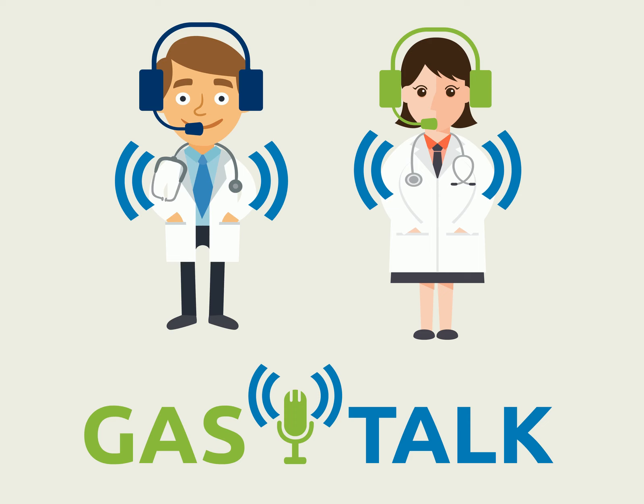I hate to laugh at that — it's something serious. It sounds as though you have a lot of experience in this area. Is there anything else anesthesia clinicians need to know about low and minimal flow? Gas analyzers need to be carefully calibrated, and the anesthesia equipment must have preventative maintenance performed on a regular basis — at least annually. And we cannot forget the anesthesia vaporizers themselves. They need to be calibrated at the same low flow levels that we will be running.